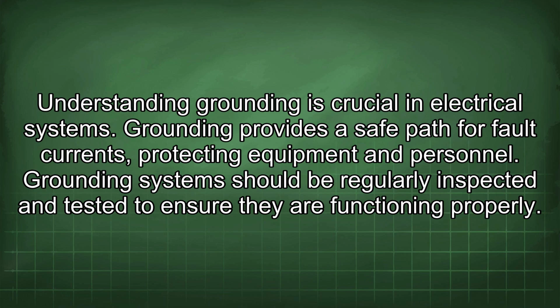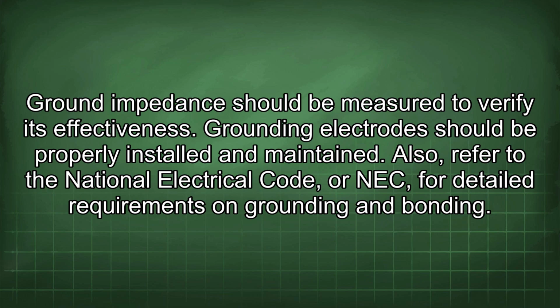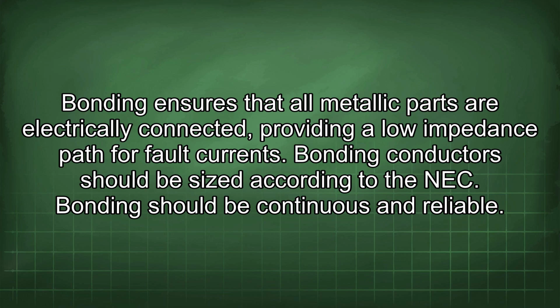Grounding systems should be regularly inspected and tested to ensure they are functioning properly. Ground impedance should be measured to verify its effectiveness. Grounding electrodes should be properly installed and maintained. Also, refer to the National Electrical Code, or NEC, for detailed requirements on grounding and bonding. Bonding ensures that all metallic parts are electrically connected, providing a low impedance path for fault currents. Bonding conductors should be sized according to the NEC. Bonding should be continuous and reliable.